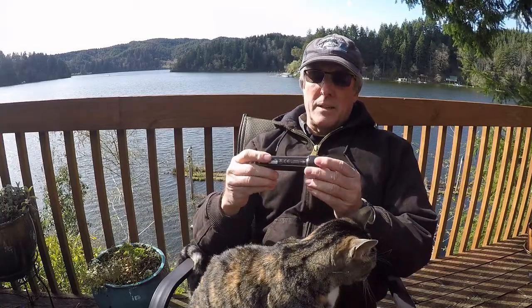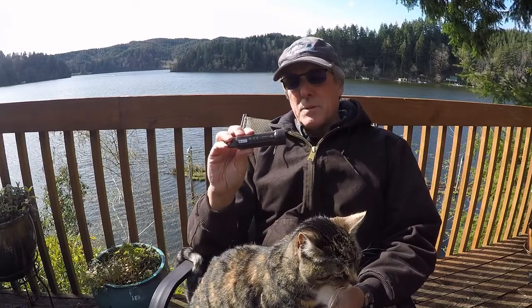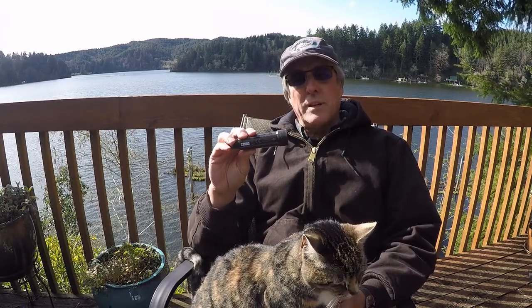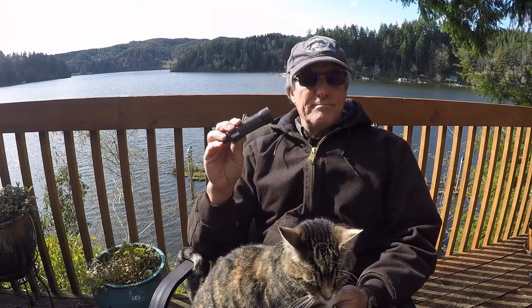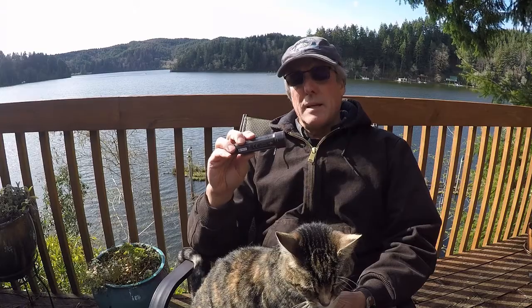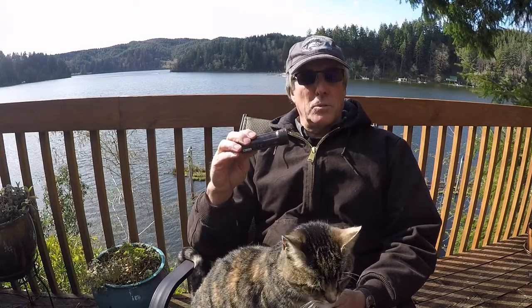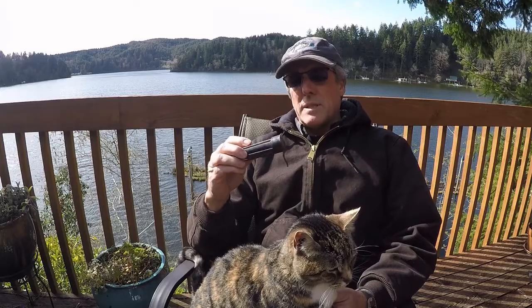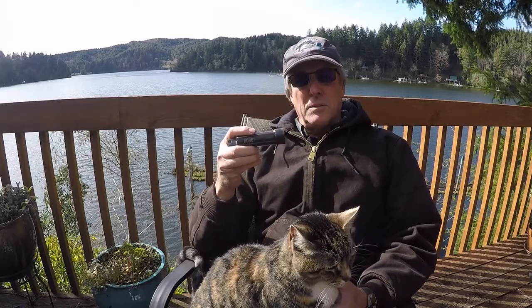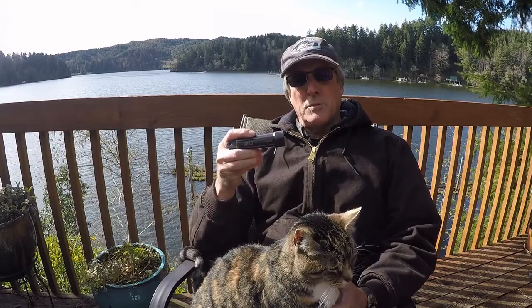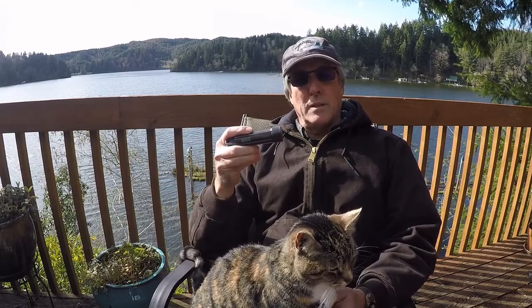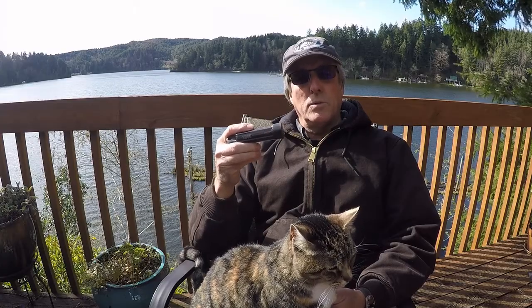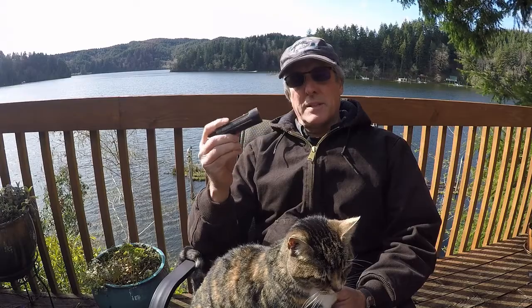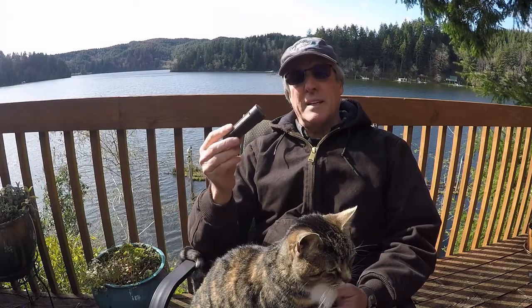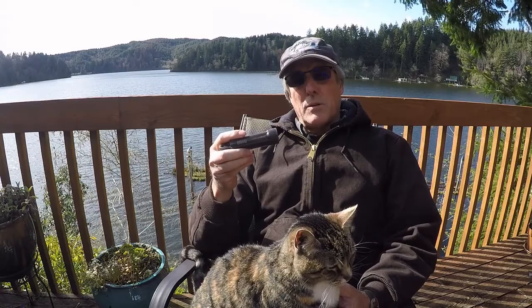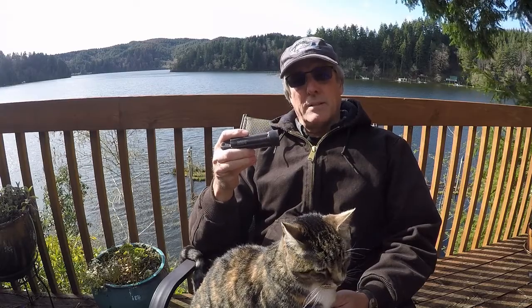So in this particular case, what we try to do is set this up to record the temperature once every hour for all those months from June through September. Usually we don't do it in the winter time because the temperatures are cool enough that it isn't a problem. So today what we're going to do is show you how to set this up in the first place, as far as being able to program it to take the readings when you want the readings to be taken. For instance, we're going to use once every hour, and then you can also program it to turn on at a particular time, turn off at a particular time if you want it.